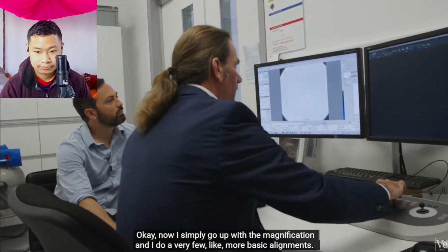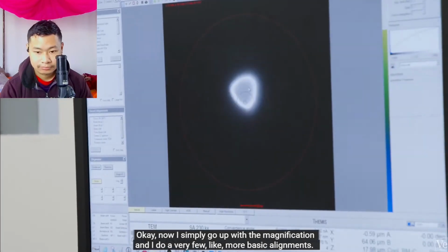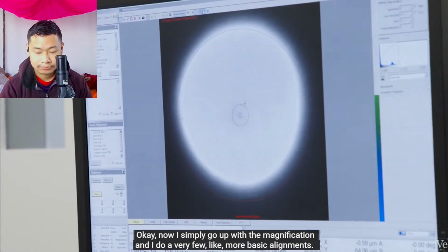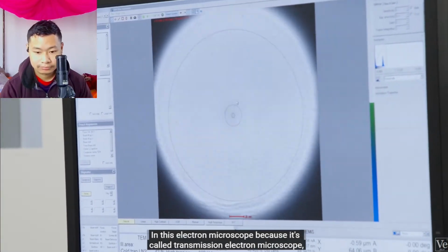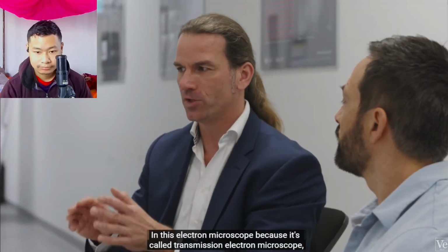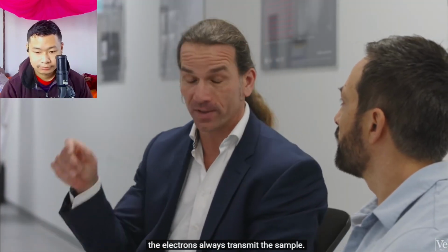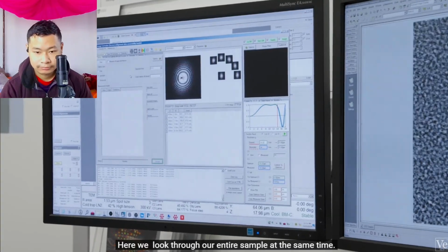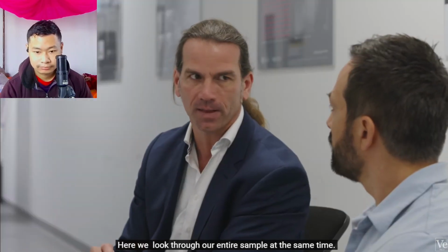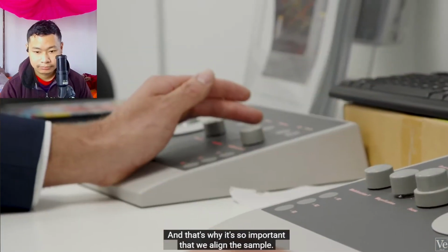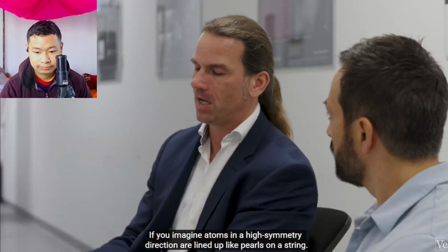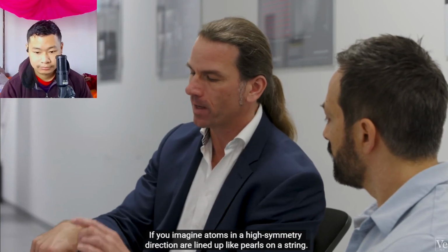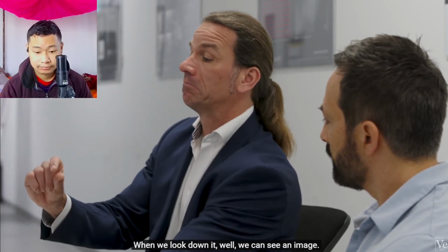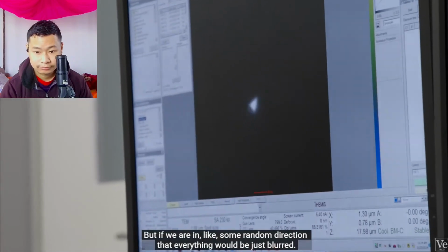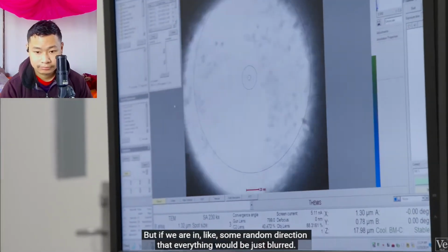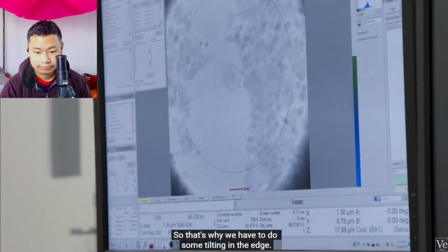Okay, now I simply go up with the magnification and I do a few more basic alignments. In this electron microscope, because it's called transmission electron microscope, the electrons always transmit through the sample. Here we look through our entire sample at the same time. And that's why it's so important that we align the sample. If you imagine atoms in a high symmetry direction are lined up like pearls on a string, when we look down it, well, we can see an image. But if we're in some random direction, then everything will be just blurred. So that's why we have to do some tilting in the end.